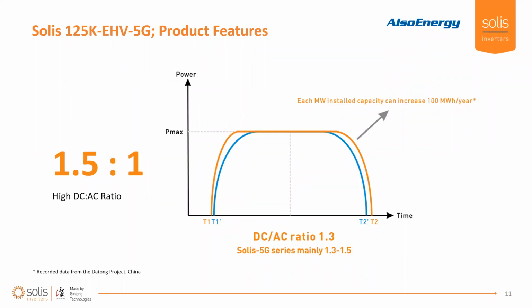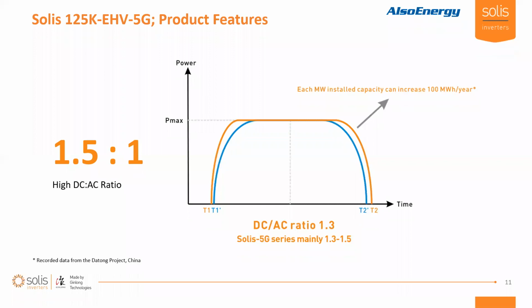This particular inverter's 1.5 to 1 DC-AC ratio is just not an issue. It really allows you to design your systems to really up that power density, to get better cash flow on some sites where you're not so much worried about clipping, but more worried about maximizing your return on cash flow. Typically we see these systems installed mainly around 1.3, where your clipping is relegated to less than 2% or so. But if you want to up that IRR, you might raise the DC-AC ratio, and this inverter is not going to have an issue with that.